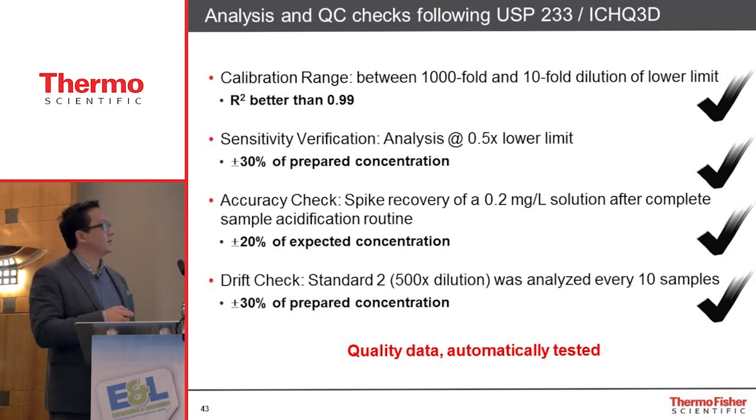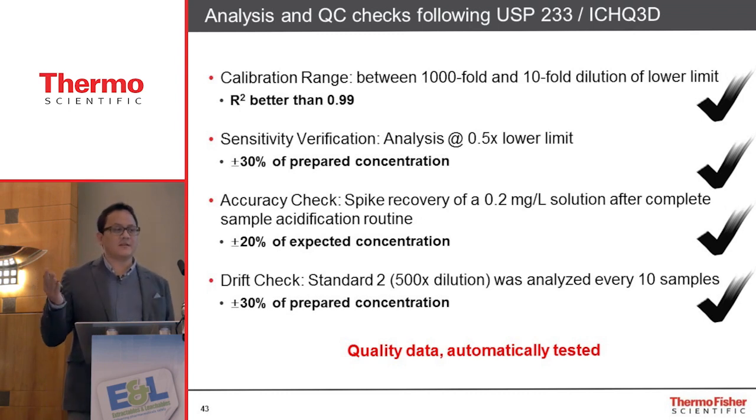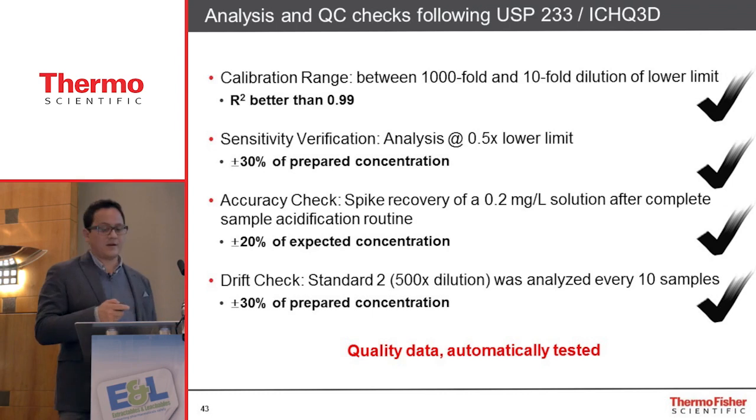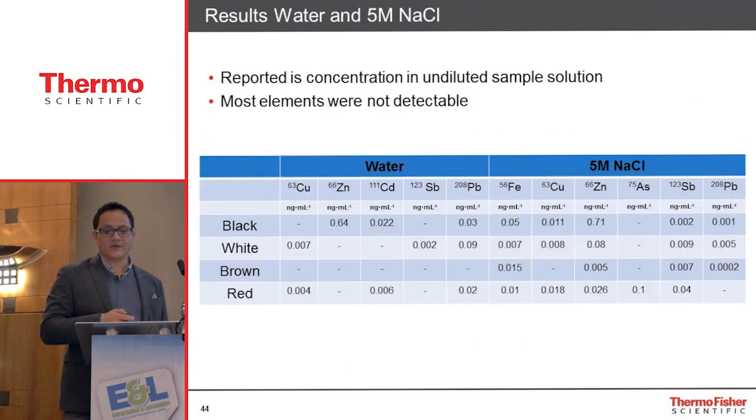It tests all of your calibration range, the linear dynamic range, the sensitivity verification, the accuracy check, and it also monitors drift across the day to ensure that all of the QC criteria are reported for the data. It probably doesn't come as much of a surprise to many of you who are more familiar with this area than I. There wasn't a high degree of metals that were extracted from the O-rings, thankfully.